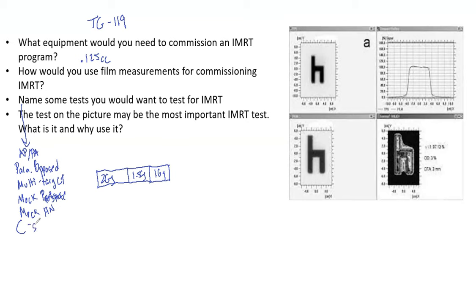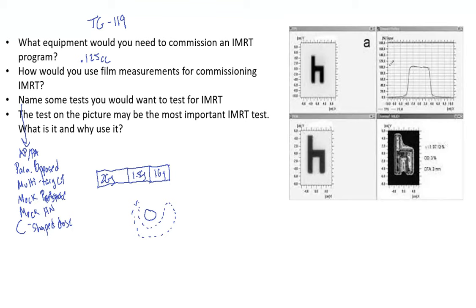Another option TG-119 mentions is a C-shaped dose distribution. Imagine you have a spinal cord and you want to treat all around it — if you can wrap dose around that spinal cord, that is the most difficult distribution to achieve. Use film to verify it and place a chamber inside the spinal cord region to verify it's not overdosed, then you can feel very good about moving forward with your IMRT program.